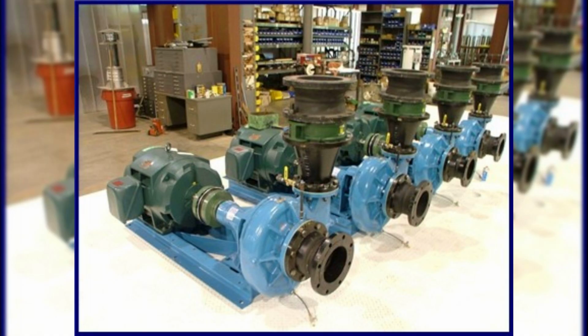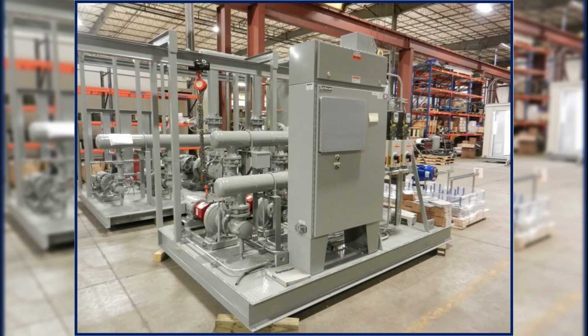The motors for these pumps are drip-proof and also come with regreasable bearings for long-term reliability. Now let's go over variable speed packaged pumping systems, a key feature in SCA projects. These systems are factory assembled, which means they arrive ready to go, offering high efficiency, built-in redundancy, and much smoother commissioning. The base and frame are built on a steel inertia base with spring isolators. This not only minimizes vibration but can also double as a concrete form if needed.